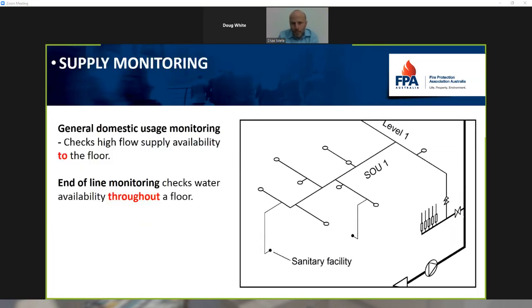I just need to make the point here that there are 2 forms of what we call monitoring. We're using this term monitoring now, and we've typically called monitoring in fire systems being electronic valve monitors. Now we're using the water itself to monitor the availability of protection. The 2 forms are, the first one is the general domestic usage of the water. So in other words, every time you have a shower or open a tap, it tells you that there's water to the floor. You've got water in your floor in your building.